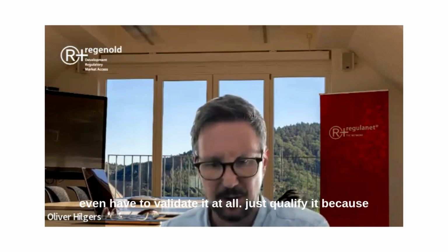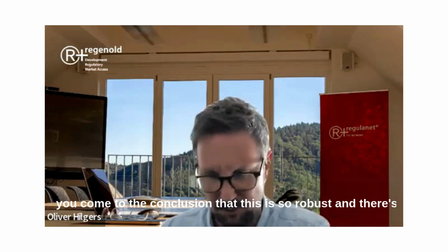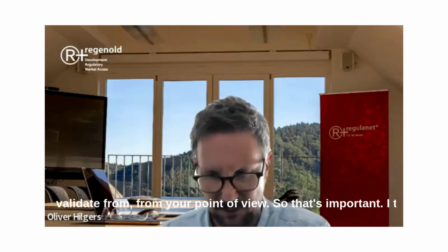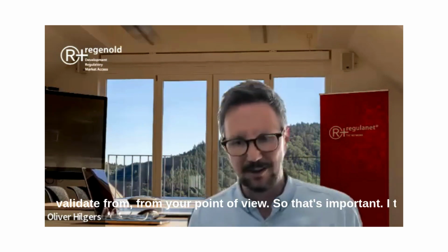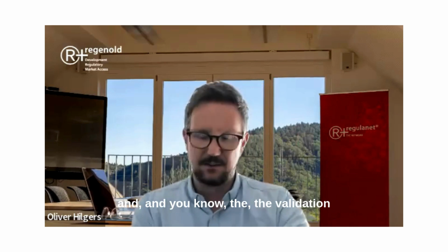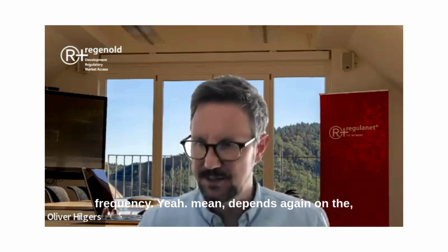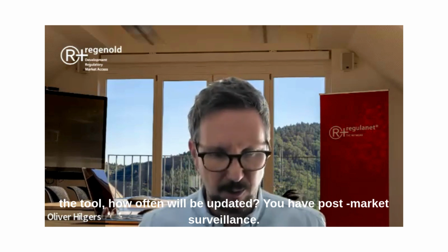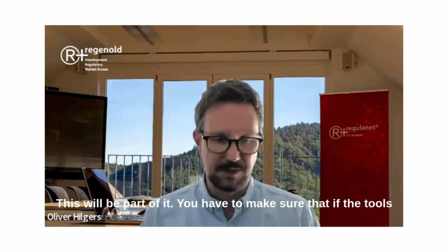You just qualify it because you come to the conclusion that this is so robust and there's no risk that you just use it, because there is nothing to validate from your point of view. So that's important, I think, to mention when we talk about this risk-based approach. And the validation frequency, I mean, it depends again on the tool, how often will it be updated. You have post-market surveillance. This will be part of it.